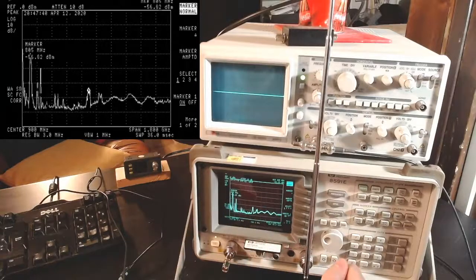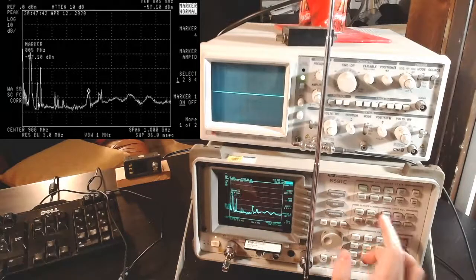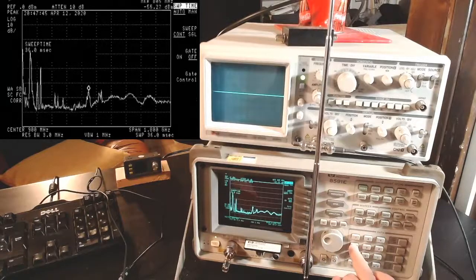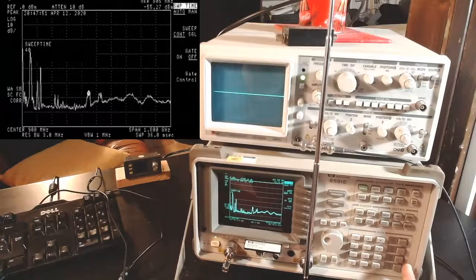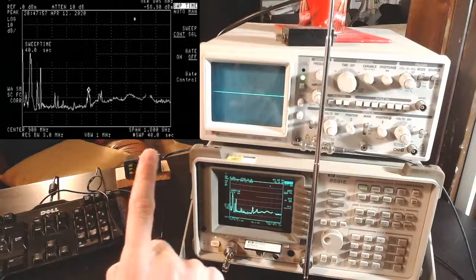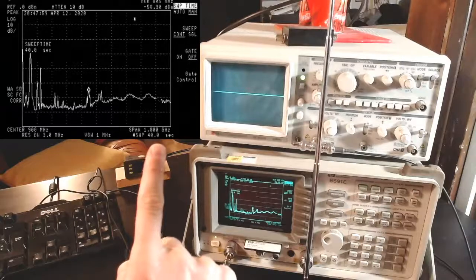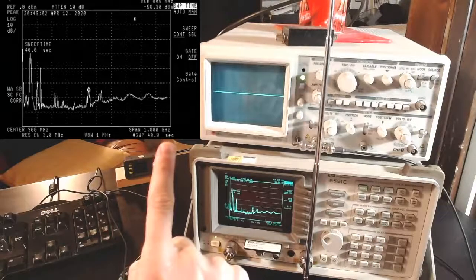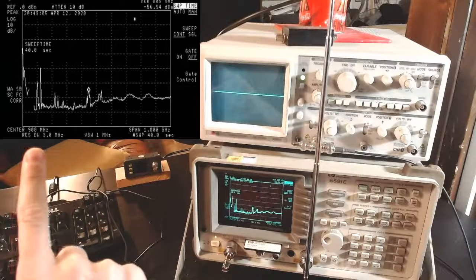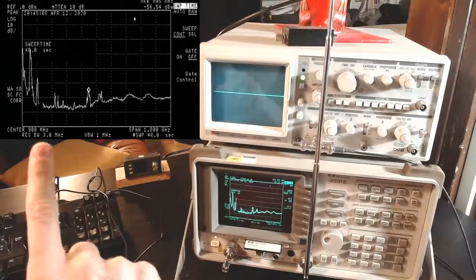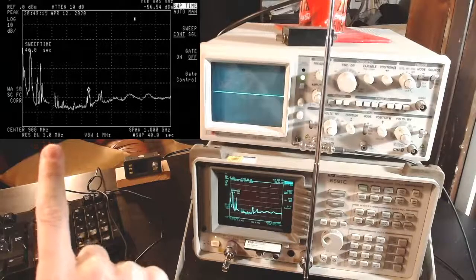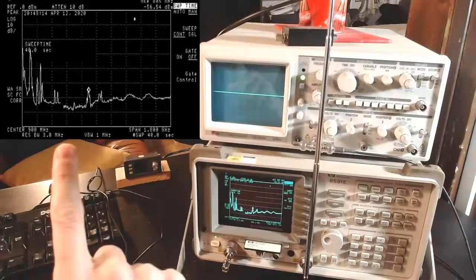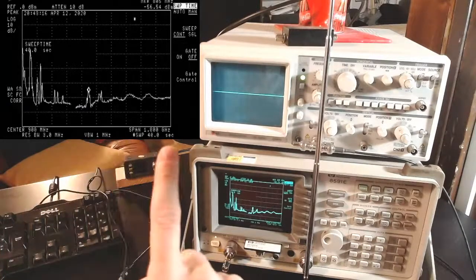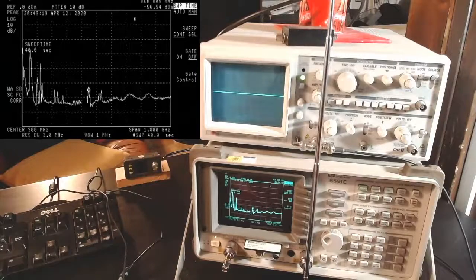So it's very fast. I'm going to slow this a lot. Let's put it, for example, at 40 seconds. 40 seconds, so much slower, and now it's much clearer. You see here the sweep action, so the spectrum analyzer is sweeping the spectrum at a much slower speed, and we can see here where it is currently observing the spectrum, right? It's advancing slowly. It does one entire sweep in 40 seconds. So that's the meaning of this.